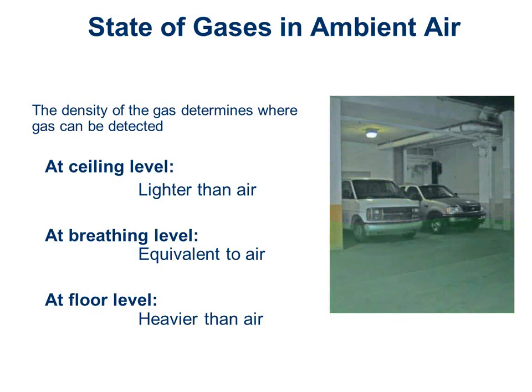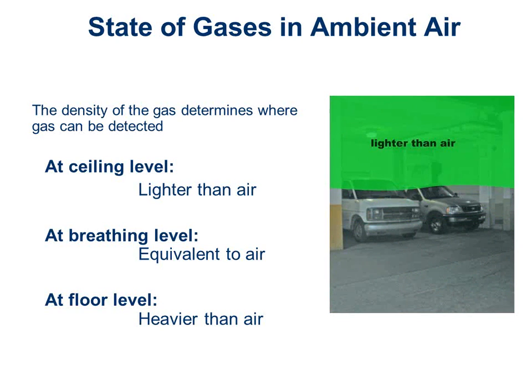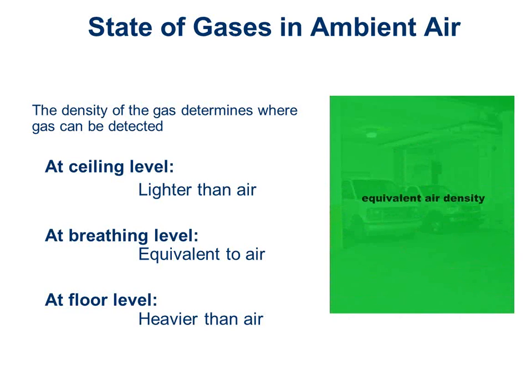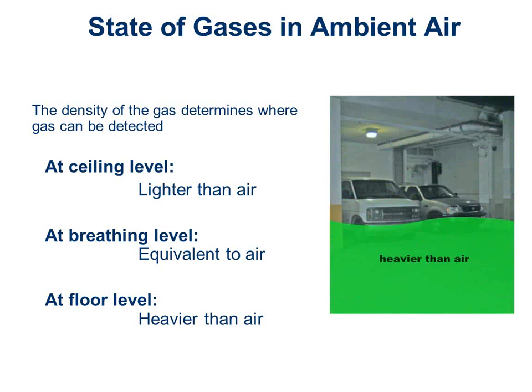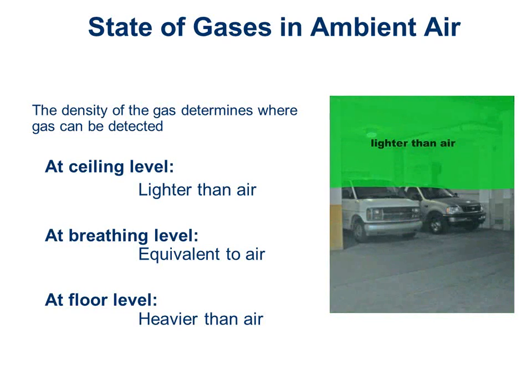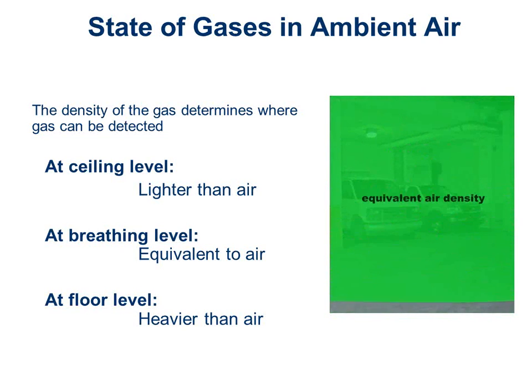If it's about the same weight as air, I want the sensor in the breathing zone, 4 to 6 feet off the ground, because I'm trying to protect people, and that's going to give me the first notification of that. If my gas is heavier than air, I want my sensor at the ground, because the gas is going to pool at the ground, so I might as well find it down there first instead of waiting until it gets higher up, right? And then if it's lighter than air, I'll measure up at the top of the ceiling, right?